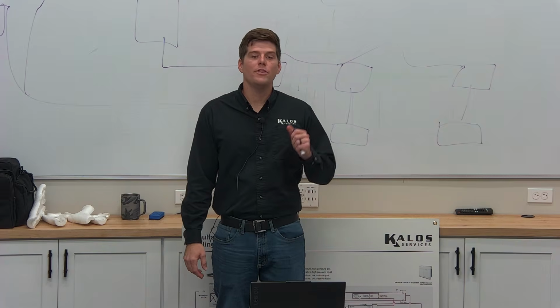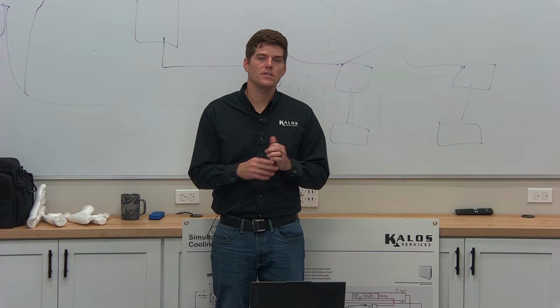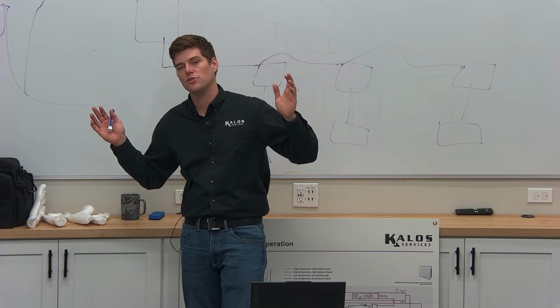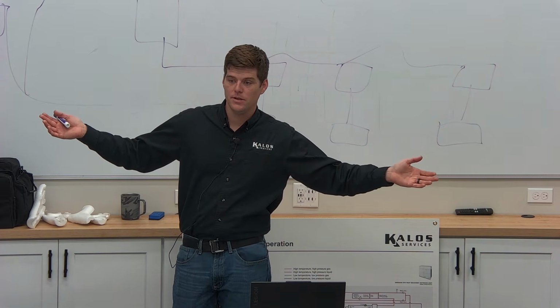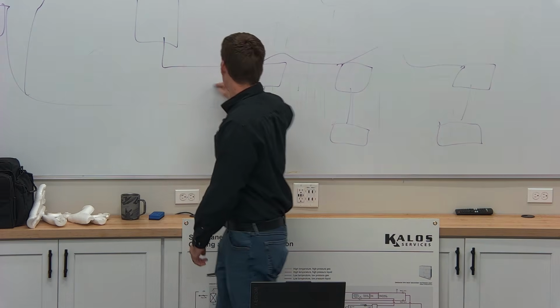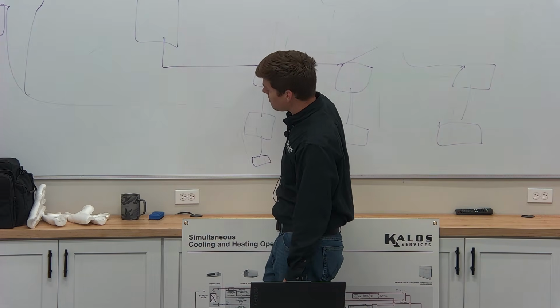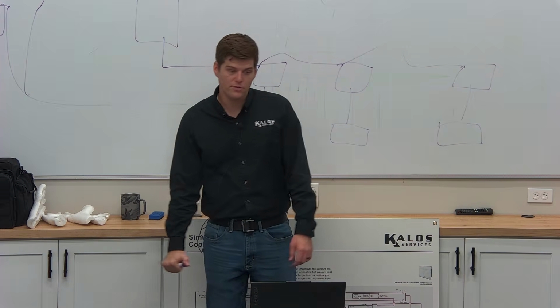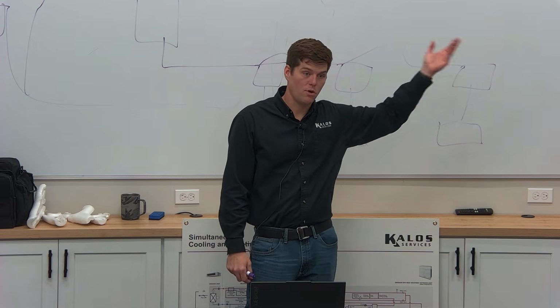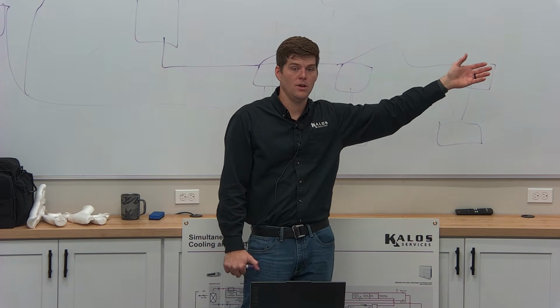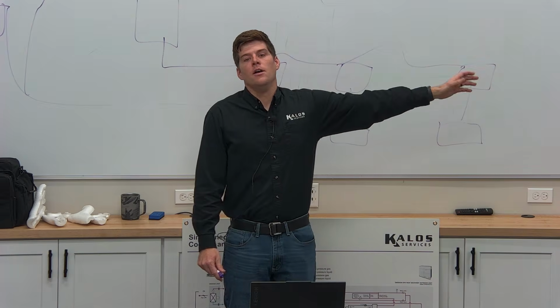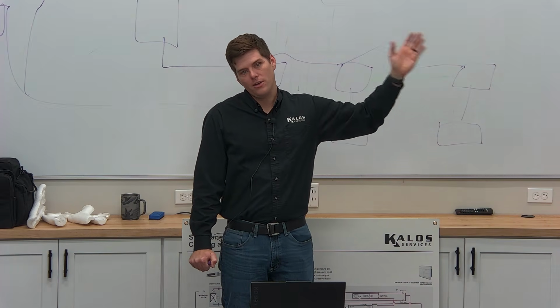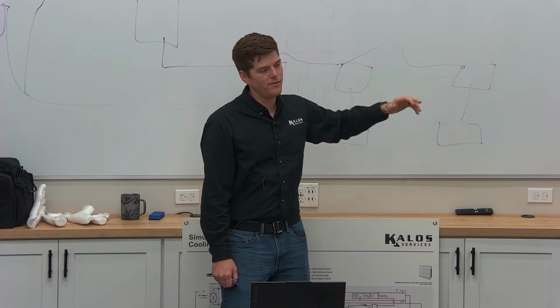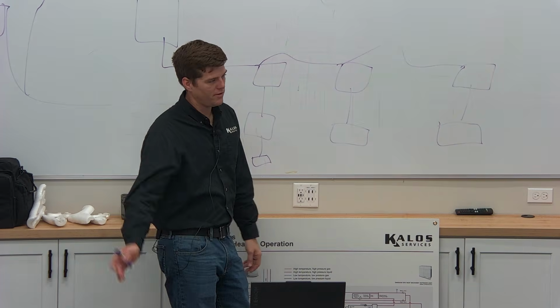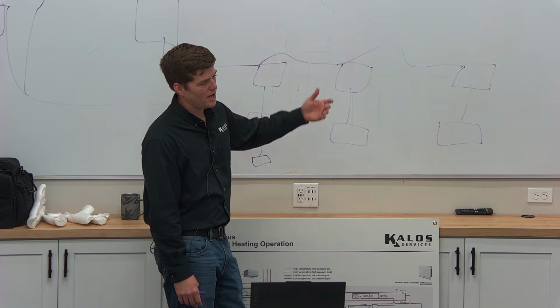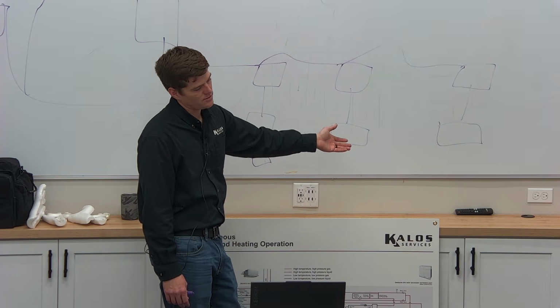If it's wired in. With that being said, let's not get lost in the weeds here, guys. It's just 2 wires, right? The system talks to the indoor units or the BS boxes. The BS boxes talk to the indoor fan coils. If you do a count on the outdoor unit, which we'll walk you through when we actually do a startup on these, I hope to have most of you there, you'll see how to do that. You push some buttons and you say, okay, I have 15 fan coils. My outdoor unit sees 15 fan coils. I'm good to go.